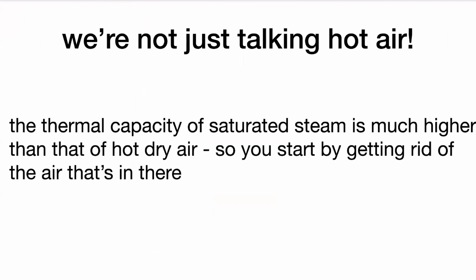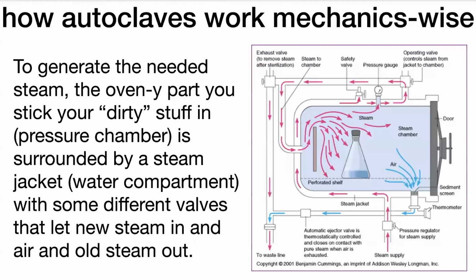So you start by getting rid of the air inside. There's a series of valves where you can pump steam in and push air out, because you want a saturated environment inside that chamber that's very humid. You get this equilibrium where the steam gets into all the nooks and crannies of the container surfaces, rather than air blocking things.